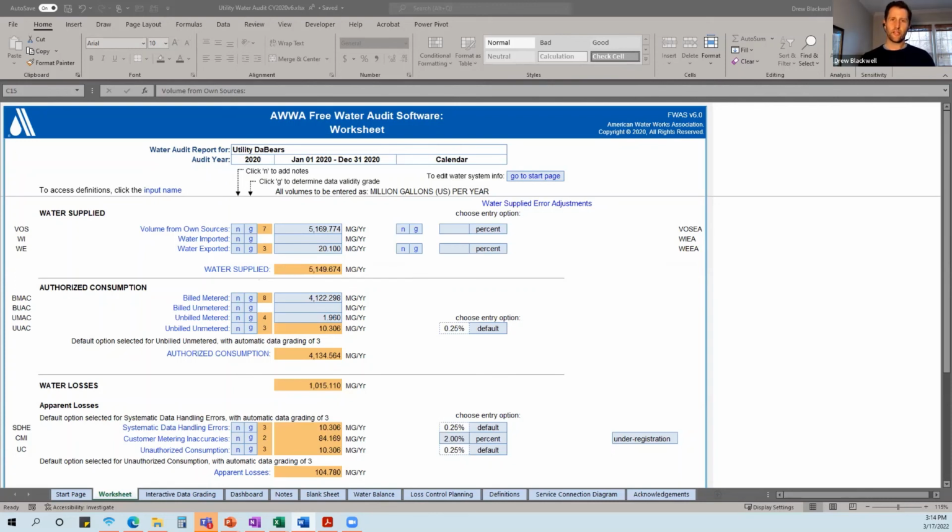That's a precise and independent measurement in the current field conditions against the subject meter. And the other test is electronic calibration. That's the alignment of the flow range conversion with signal span output. So checking that 4 to 20 milliamp signal span and the SCADA output. So do either of those test methods sound familiar?